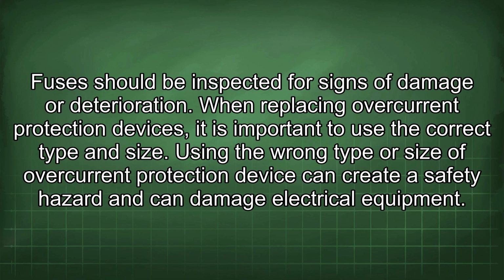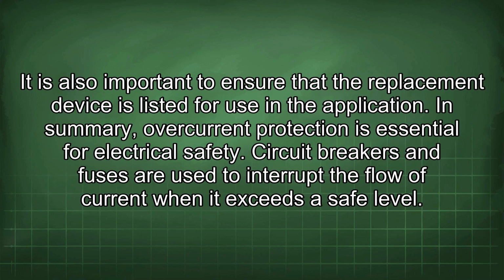When replacing overcurrent protection devices, it is important to use the correct type and size. Using the wrong type or size of overcurrent protection device can create a safety hazard and can damage electrical equipment. It is also important to ensure that the replacement device is listed for use in the application.